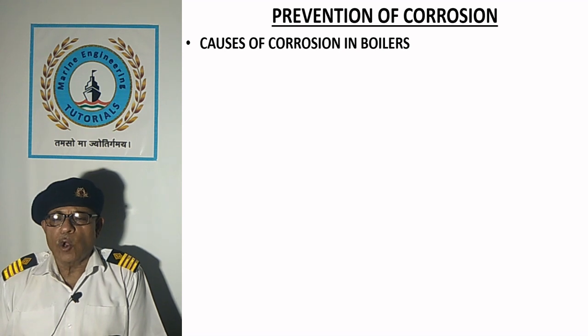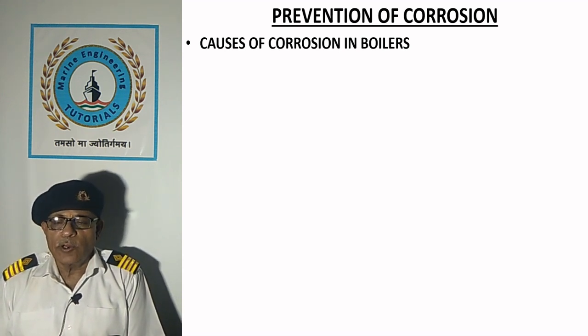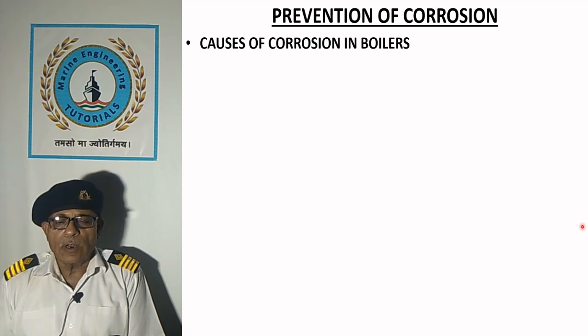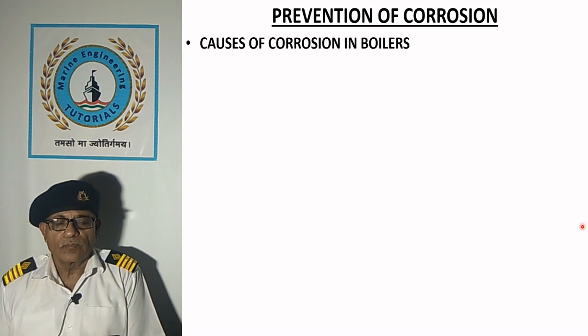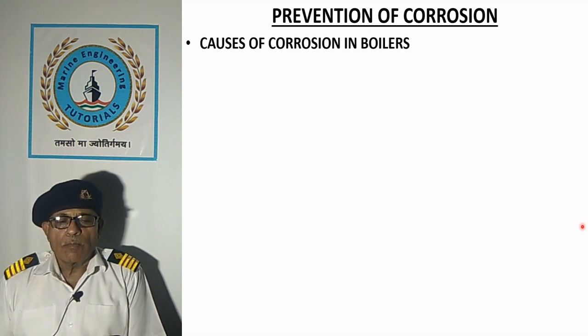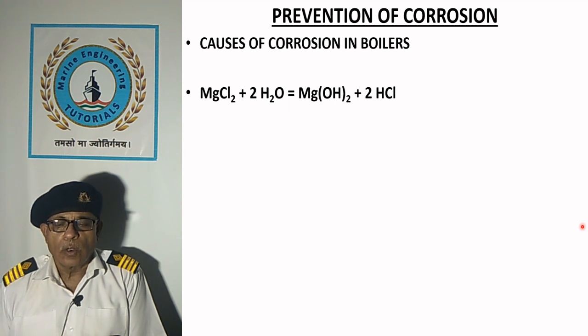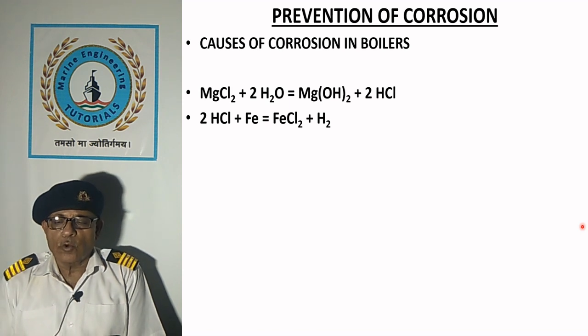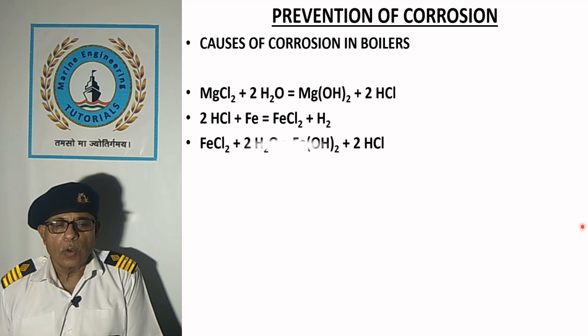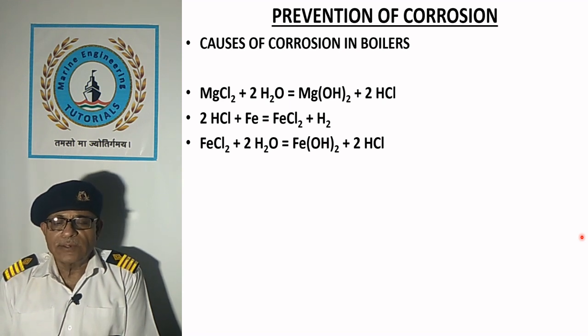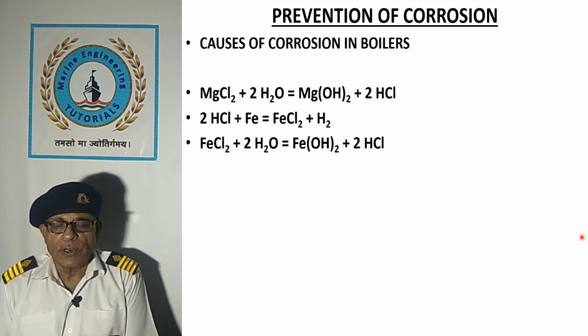Causes of corrosion in boilers: magnesium chloride, calcium bicarbonate, dissolved oxygen, and use of vegetable or animal oil for lubrication are responsible for corrosion in boilers. Magnesium chloride is hydrolyzed to form hydrochloric acid, which starts corrosion of steel in the boiler. Hydrochloric acid is regenerated by further reaction and starts a corrosive cycle. HCl is neutralized by maintaining reserved alkalinity in boiler water by sodium carbonate, reserved phosphate and caustic soda.